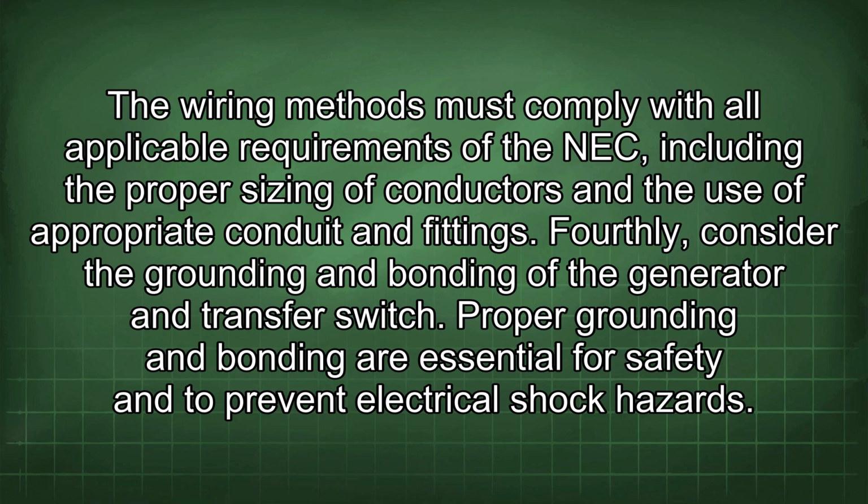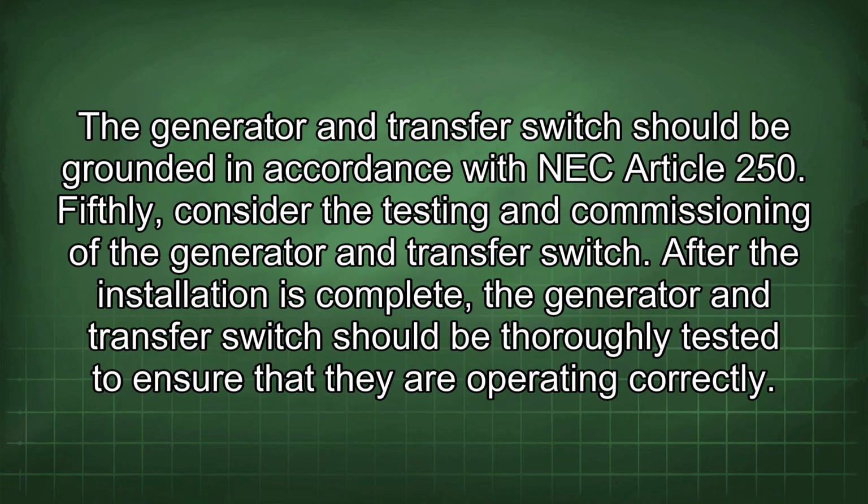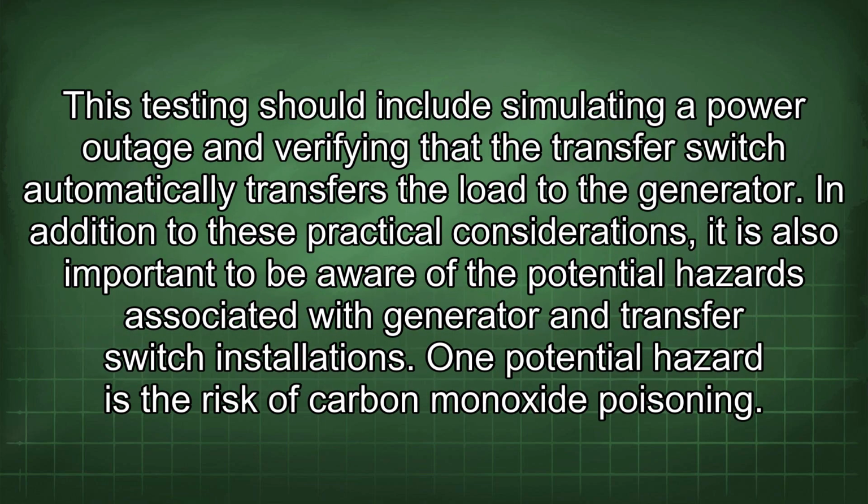Fourthly, consider the grounding and bonding of the generator and transfer switch. Proper grounding and bonding are essential for safety and to prevent electrical shock hazards. The generator and transfer switch should be grounded in accordance with NEC Article 250. Fifthly, consider the testing and commissioning of the generator and transfer switch. After the installation is complete, the generator and transfer switch should be thoroughly tested to ensure that they are operating correctly.